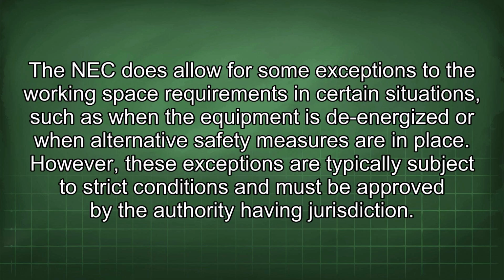Another common question is whether the working space requirements can be reduced or waived in certain circumstances. The NEC does allow for some exceptions, such as when the equipment is de-energized or when alternative safety measures are in place. However, these exceptions are typically subject to strict conditions and must be approved by the authority having jurisdiction.